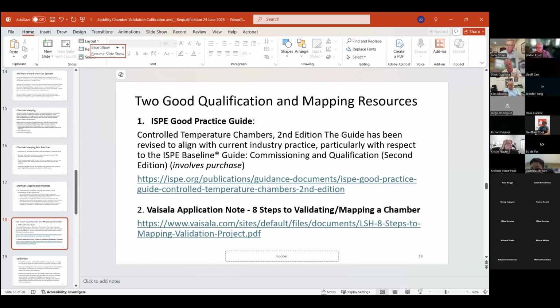It'll have to be remedied one way or another, but while we often support the local crews in repairing or revising the function of the chamber to meet the changing customer needs, I've found that the documentation needed to justify those changes is generally hard to get out of a maintenance technician. You're generally going to need those reports to be translated into something that can be used for justification in an audit and regulatory compliance. So a little bit of both, a bit from the maintenance crew, but it's always nice to have the manufacturer's support in making those justifications a little more robust if and when needed. Okay, thank you. All right, if we cleared all our questions for the moment, we'll move on to calibration.